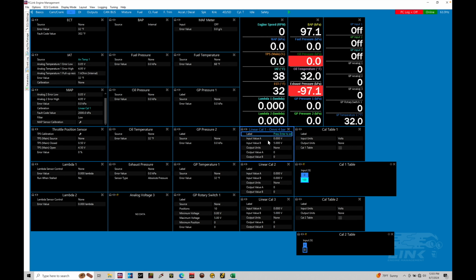The next thing here is we have an input A and B value, and then we also have output A and B. As I was mentioning, pressure sensors are a linear style sensor. They have a minimum and maximum voltage and a minimum and maximum pressure reading. We need to input that to our values here. So the input value A is our minimum voltage. The output would be then the actual sensor reading at that voltage. So minimum volt, minimum pressure.